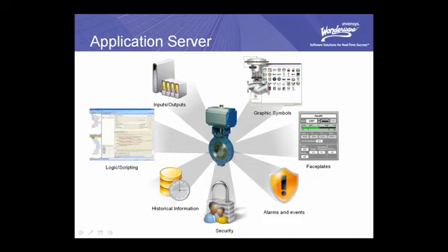It's also here, within the asset definition, that we identify what data points we want to store long-term for analysis. We can also define who can operate and interact with the device from within this definition, and that applies to both the runtime model as well as the development time or design time model. We also have the ability to configure the alarm limits for various data points associated with the device, and in the latest release of Application Server, we introduced the ability to store graphics associated with the device inside the template definition as well.